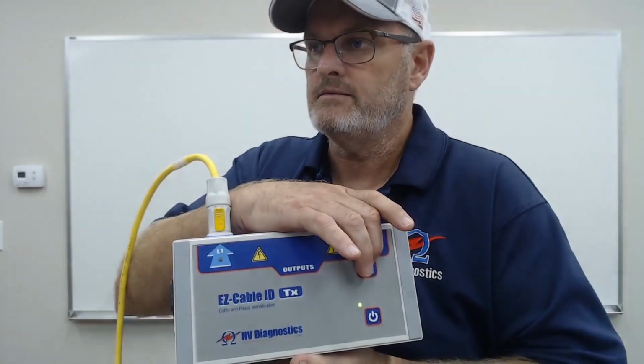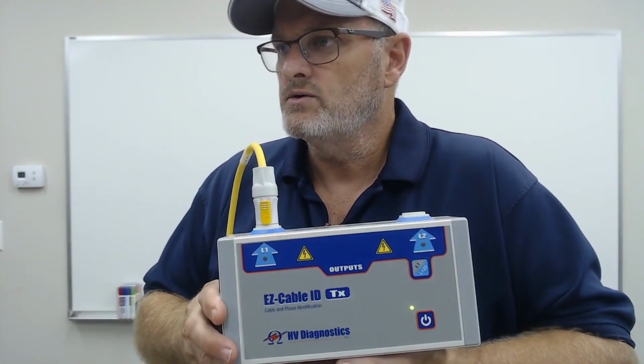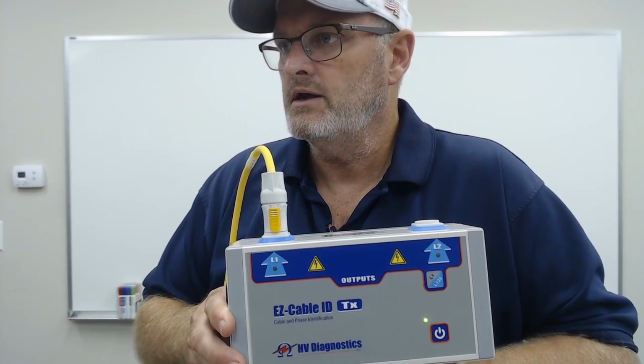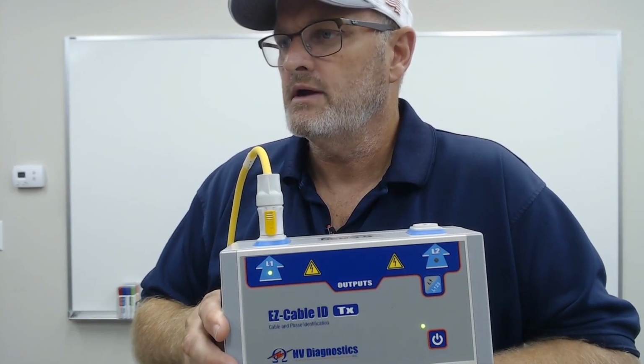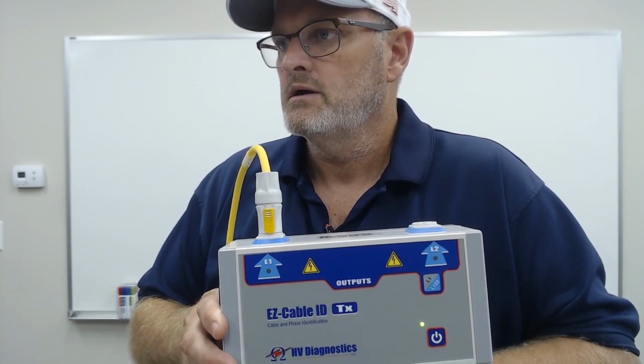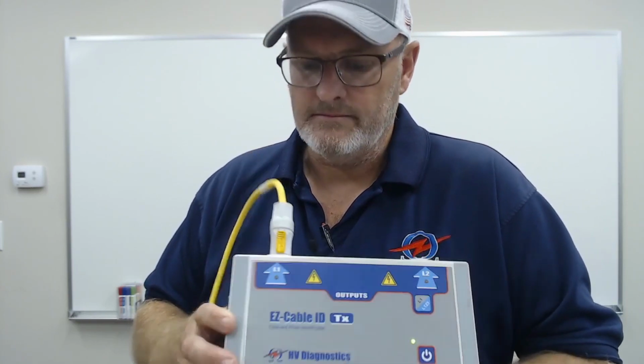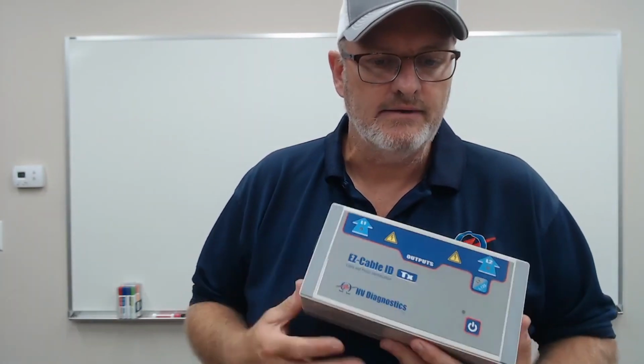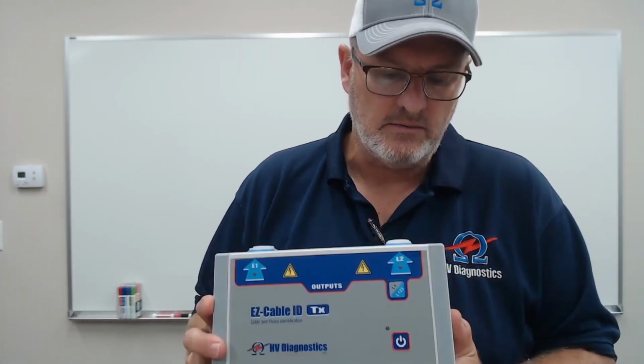So for example, if I connect this over here, go back to single-phase mode, you'll see if we short circuit the output, it goes to green. If we open circuit it, in other words, we have a bad connection, it'll go to red. There we go. All right, so that is the transmitter. Battery operated or AC operated, and that injects the signal, or the pulses, down the cable.